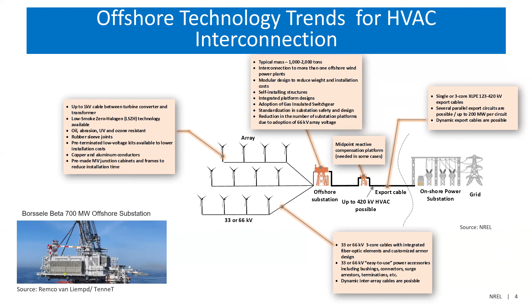And of course, there are a lot of innovations happening on the plant level, on the substation level, and in the export cable, shown here, that will allow reducing the overall cost of high voltage AC transmission. What 66 kilovolt makes possible is more advanced and more reliable collector system designs in offshore plants. Normally, 33 kilovolt plants use configuration IA, which is a single collector radial system. But with larger, higher capacity cables, different types of ring designs can be achieved, which will significantly increase reliability and availability of these collector systems. And of course, more futuristic designs such as star collection systems or multi-collector rings can also be utilized, but these are mainly at a research stage right now.